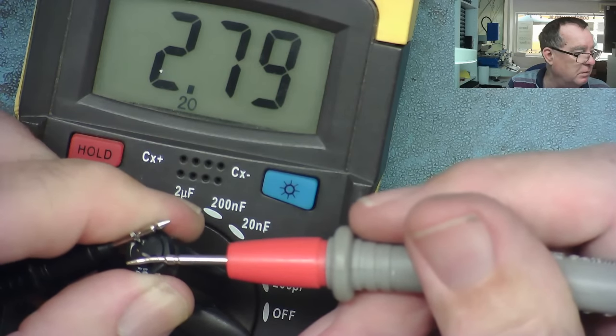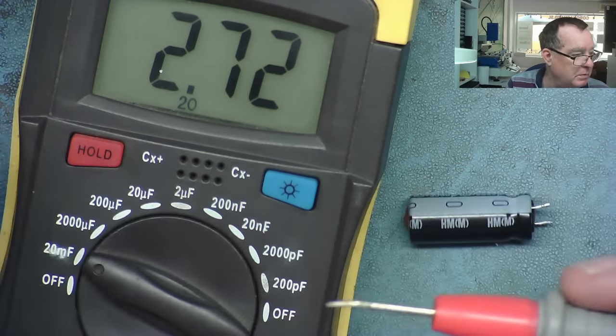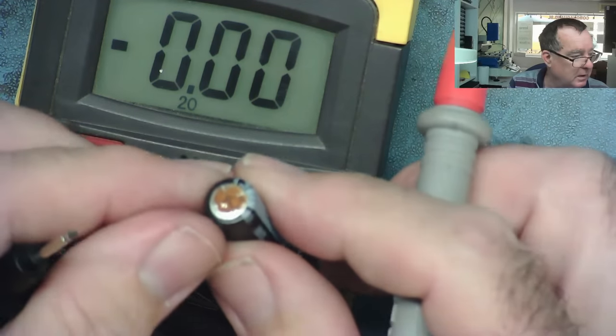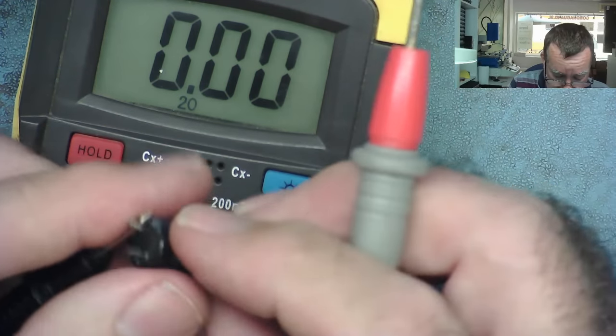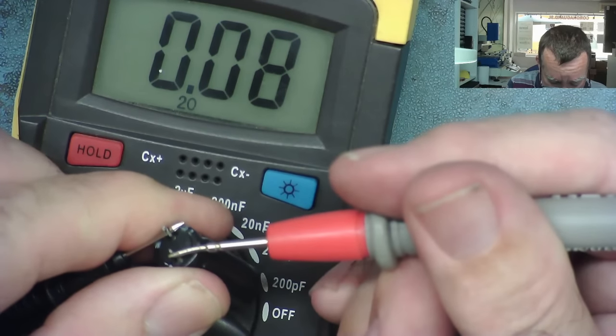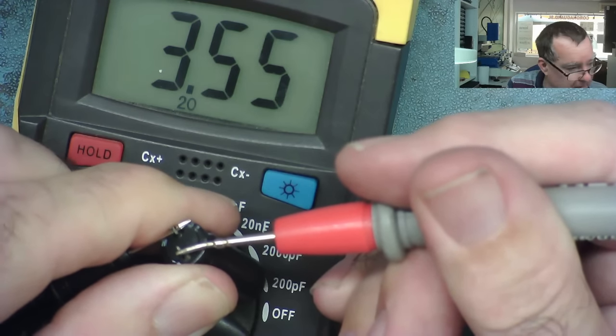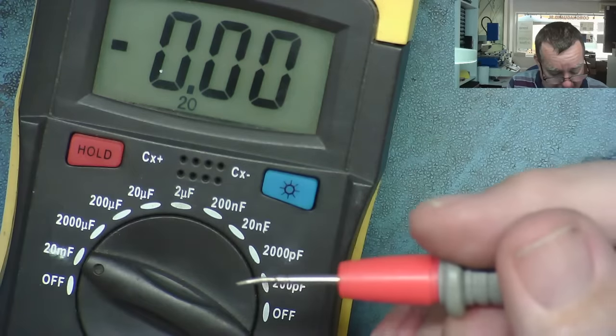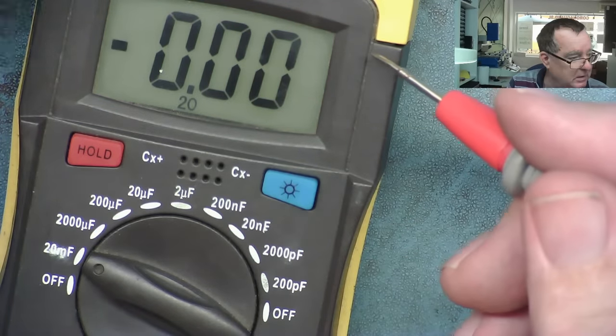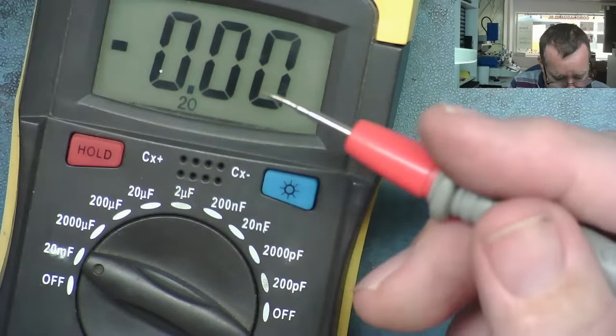That one's reading low, look at that, 2,700. So we know that's a bad capacitor, the bulged one. This is another one, reading 3,400, a bit higher than normal. Now if it wasn't for the damage on those, you might say they were good capacitors.